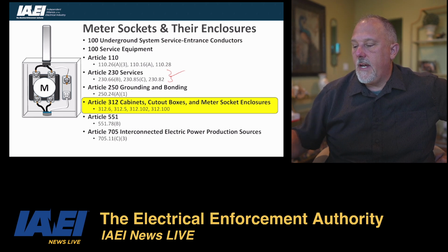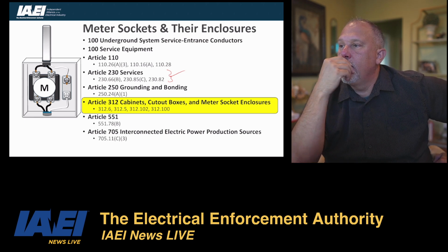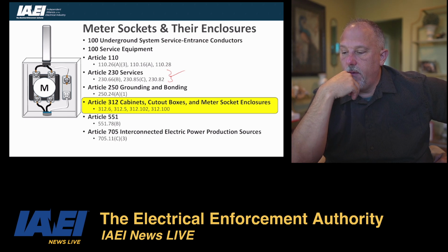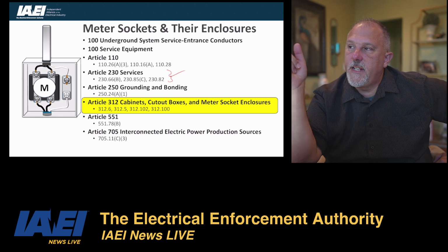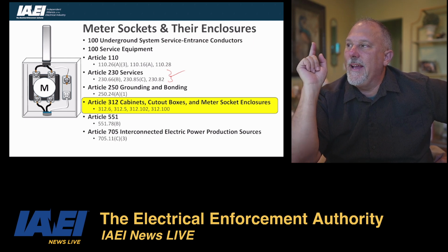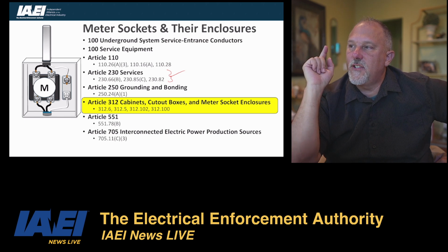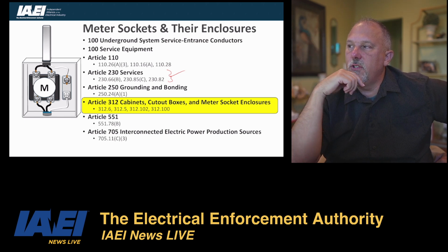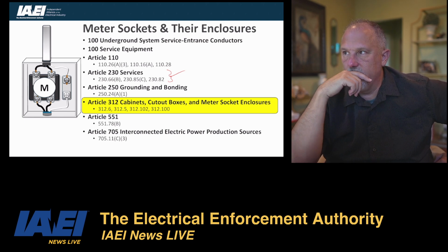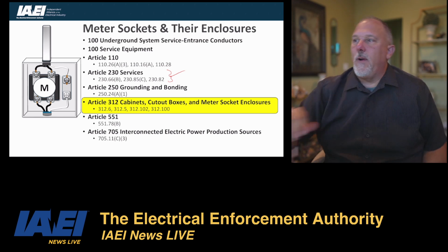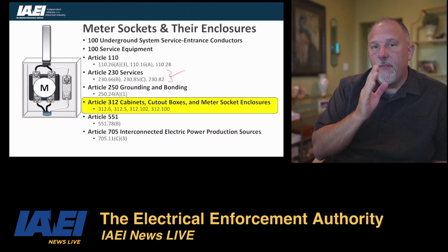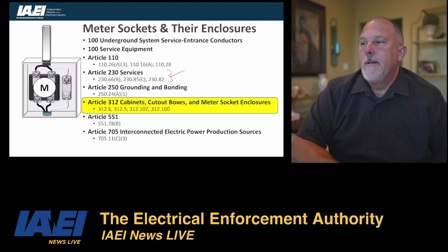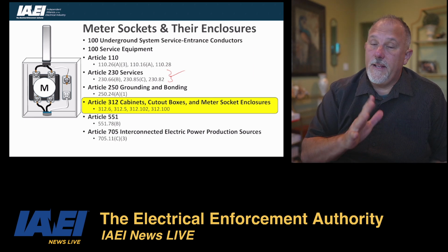The only reason I put this as a reference for meter sockets and their enclosures, I believe, is because of meter disconnect integral to the meter mounting equipment, not marked as suitable only for use as service equipment, installed in accordance with 230.82. So that's why I put that in there. But when you are thinking about service equipment, here's the other thing.